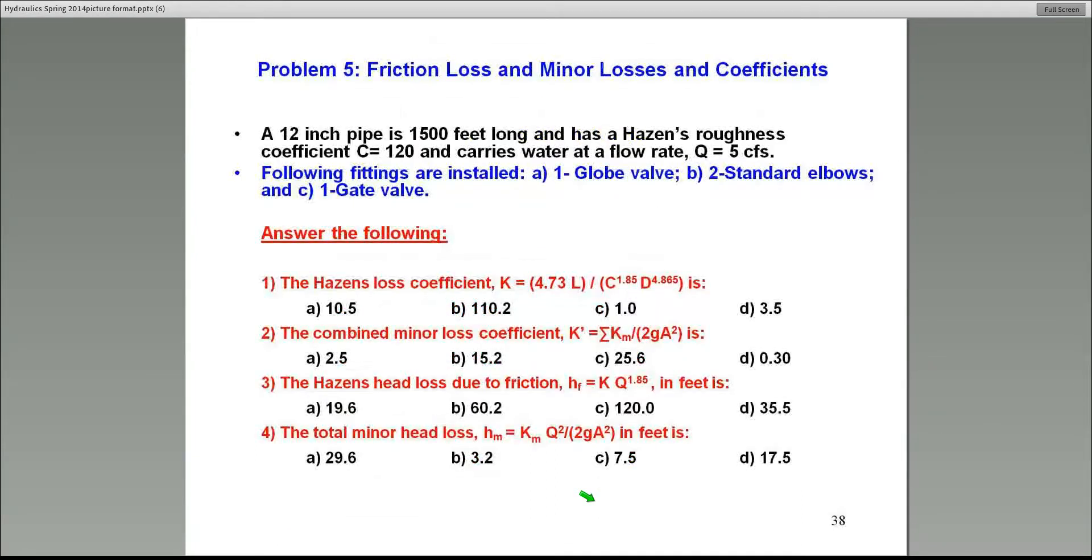I've set up a small example for you to calculate particularly these K values. And then, of course, finally, step number three to calculate the head loss in this particular pipe situation. You've got a 12-inch pipe, 1,500 foot long, Hazen's C is 120, the flow rate is given as 5 CFS. So the first thing you will do in many problems is to calculate that loss coefficient that I told you K. In this case, it's 4.73L over C to the power 1.85, D to the power 4.865.